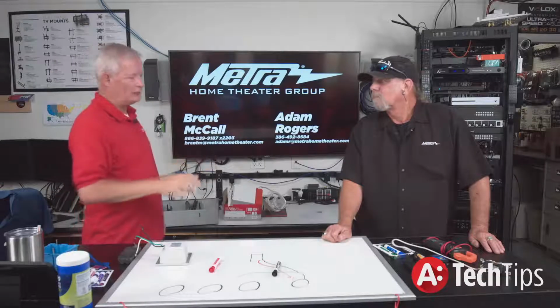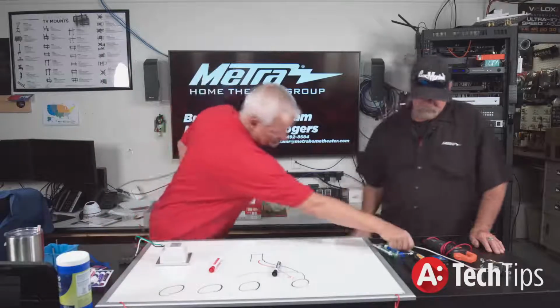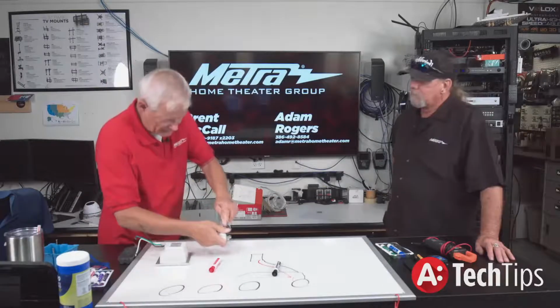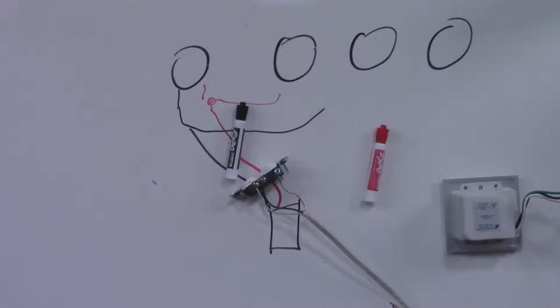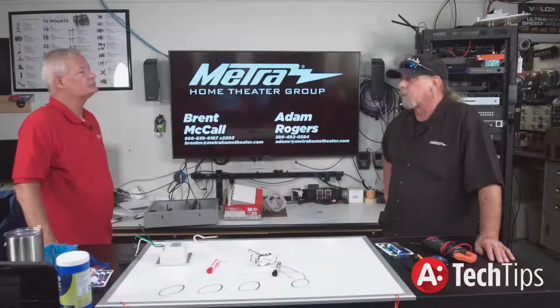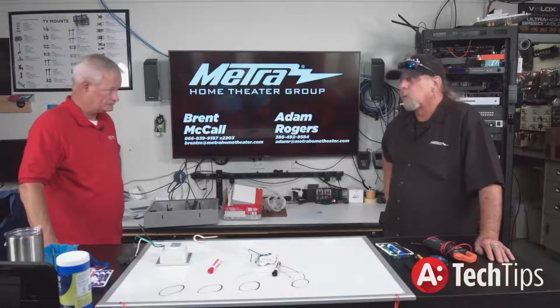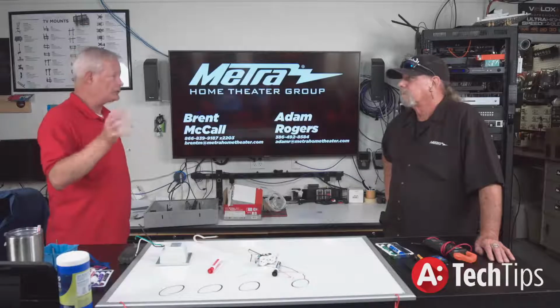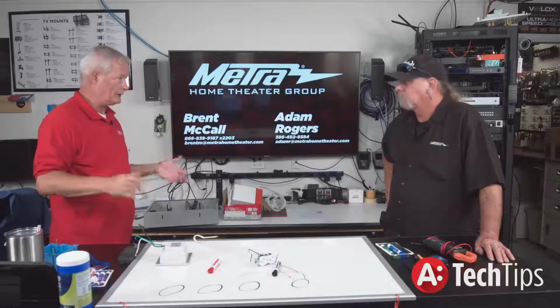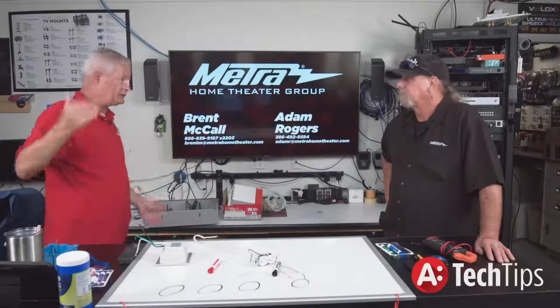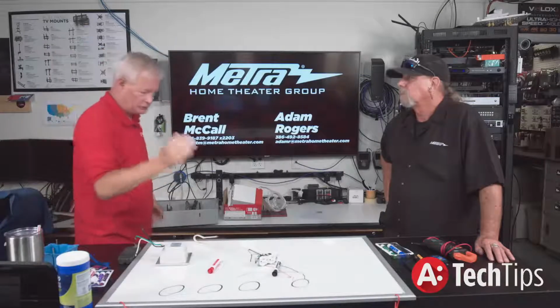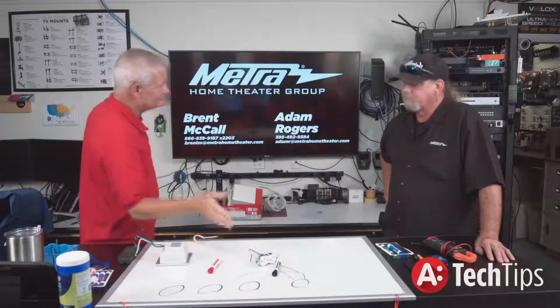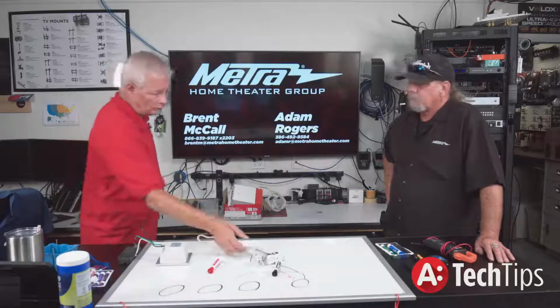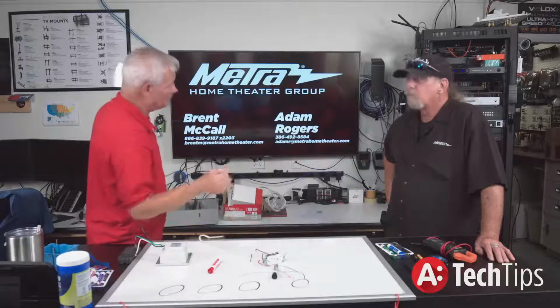When we are looking at grounding, I'm going to go back to your outlet here. How many of these can you tie together on a single 14 gauge before it's too many? You could have 5, 6, as long as you have the right wire nut and you twist the wires good and make a good connection, as long as they're twisted tight. So we're looking at 5 or 6 devices, and we are safe with that ground point because it's still only the 110 feet. It's not a combination of devices, it's still just that. And they're only going to pull, current-wise, what this is going to support anyway before the breaker trips.